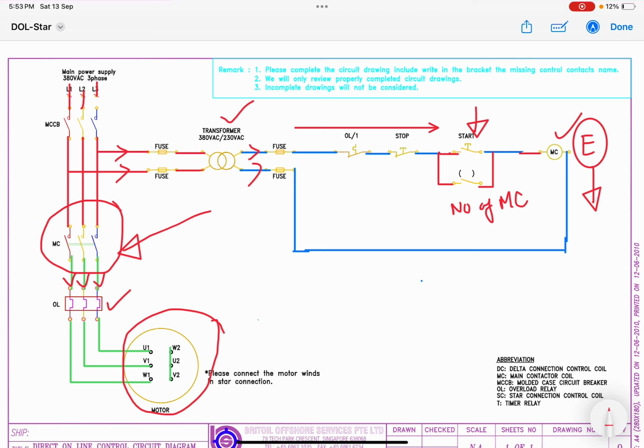So after closing its main contact, it is also going to close its holding contact here. So this contact will be closed here. So now what will happen is, even though I release this start push button and the push button is in open condition, right, power supply to my magnetic contactor is going through this fuse, through the OLR, through the stop push button, and through this holding contact, and it is still going to your magnetic contactor. So this contact we also call the holding contact, because this contact is responsible for the continuous power supply across the magnetic contactor. So this is how my circuit is going to start.